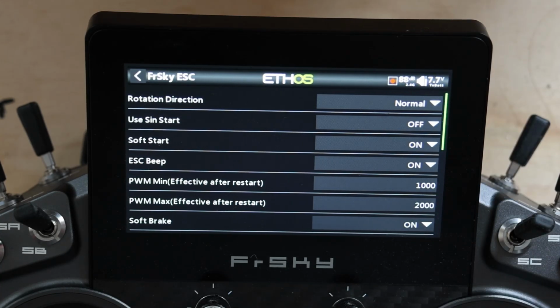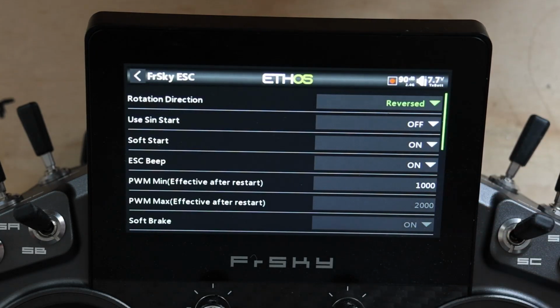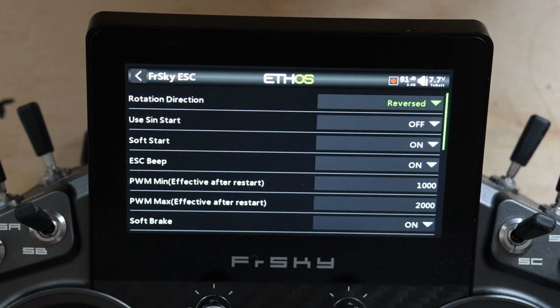We are actually going to do everything except we're going to reverse the rotation direction, because it was wrong, it was actually backwards. This is an easy way to do it, otherwise I'd have to go in, pull the motor, and swap any 2 wires to reverse direction, since there's 3 wires and swapping any 2 of them reverses it.